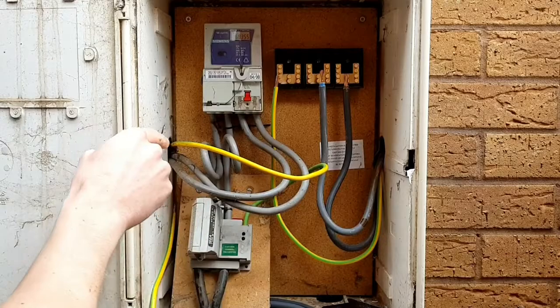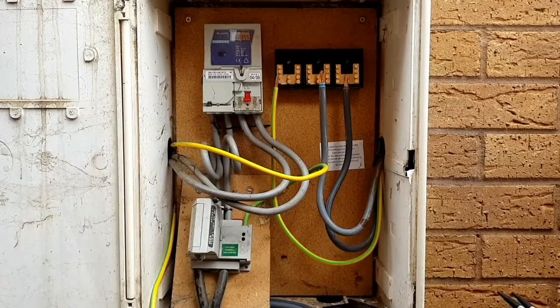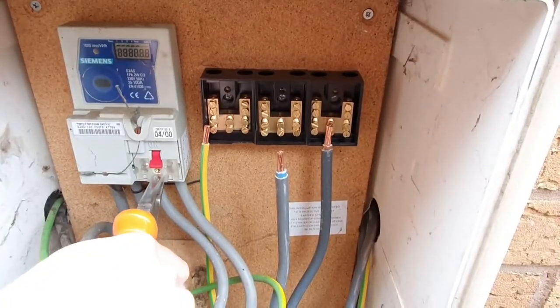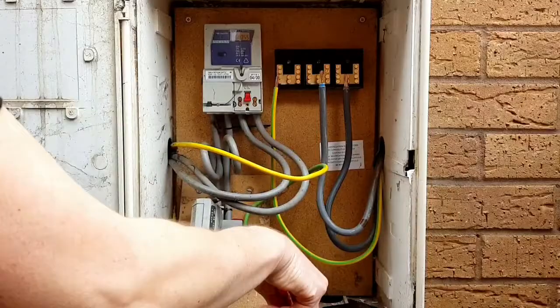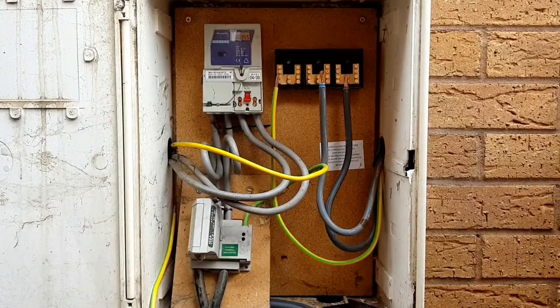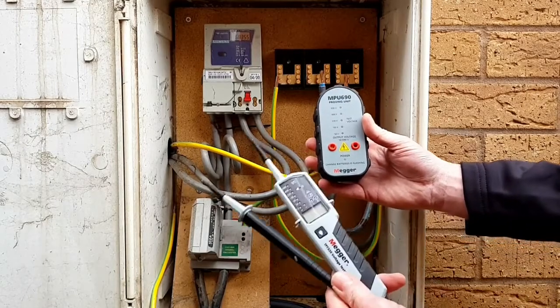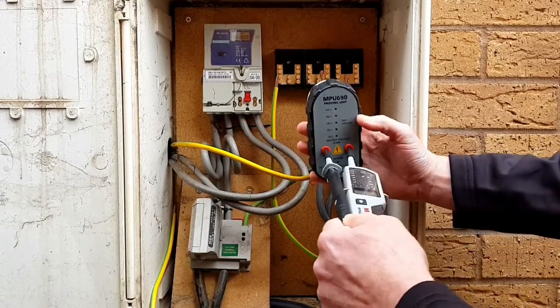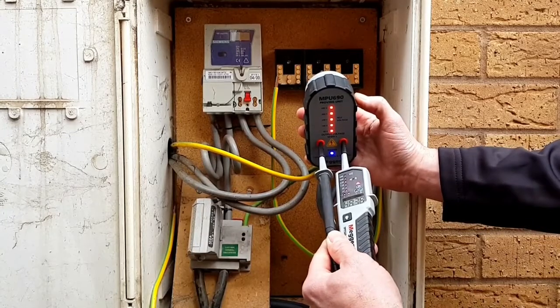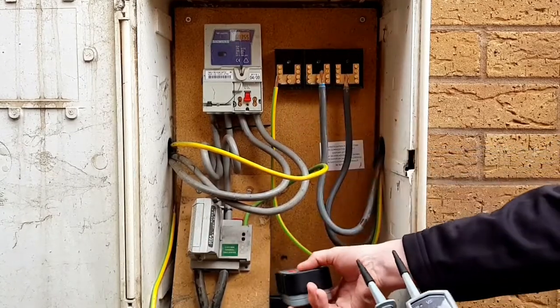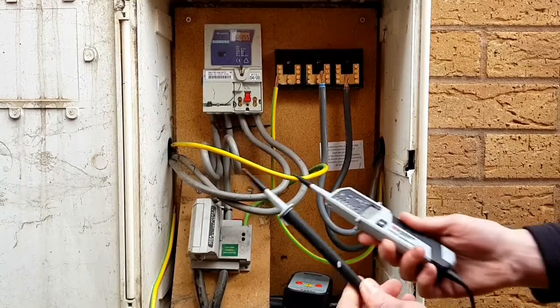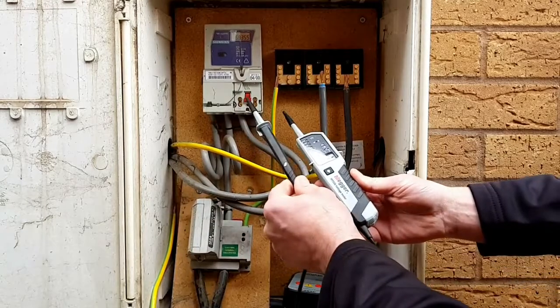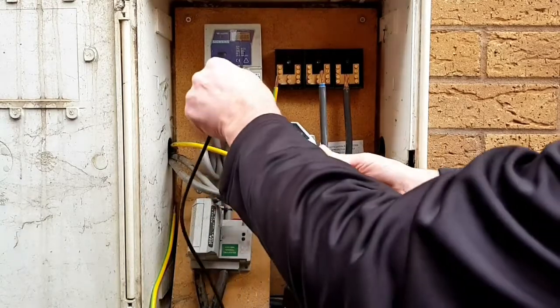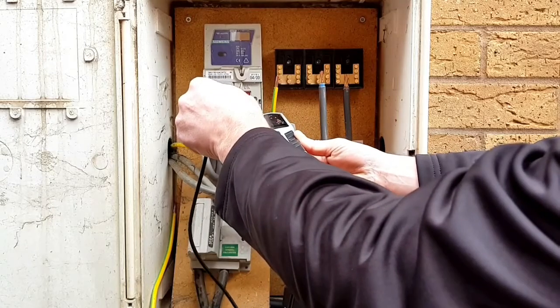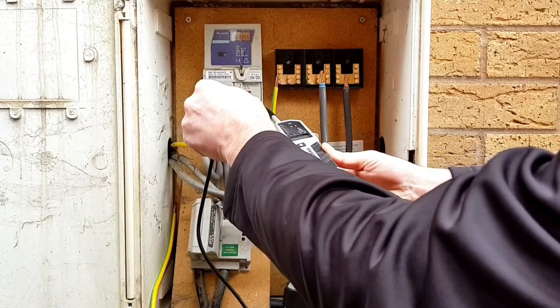So we're in a position now where we can remove the little plastic protective piece. So I'm just going to get in there with the pliers and whip that out of there. And Gary, if you'd like to now just perform the safe isolation procedure. Okay, so as always, proving unit in this case and voltage indicator. I'm going to prove that these are working correctly before we start. Okay, yeah, so we're fine with that. And then we're in, and just as always, good practice to go on the least dangerous conductor first. So onto my neutral, onto my line conductor, no voltage present, off my line conductor, off my neutral.